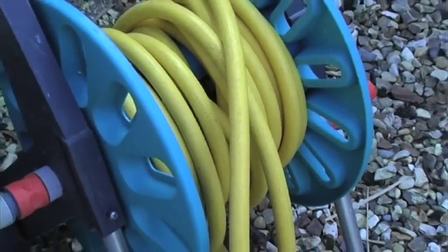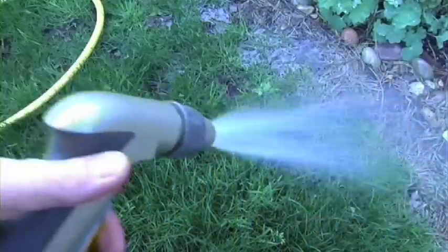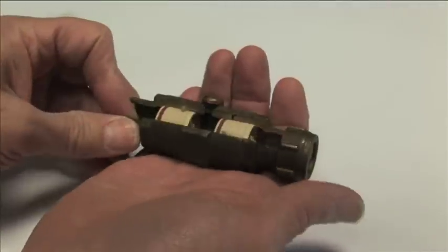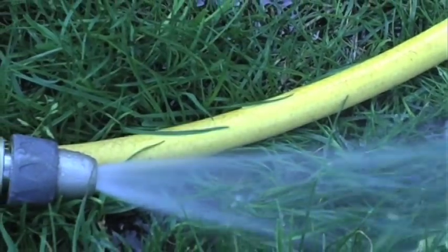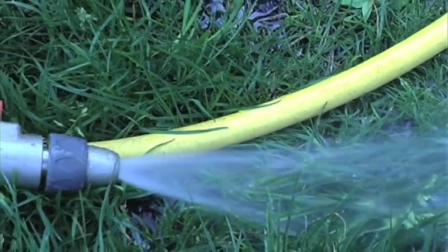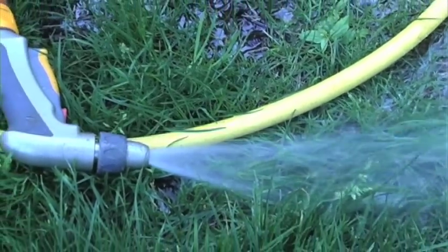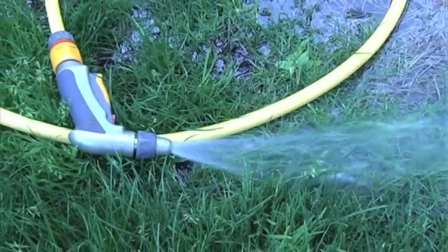In domestic premises, hose taps are usually connected directly to the water main. If mains pressure falls, to prevent backflow, they must be protected by a double-check valve — a sort of non-return valve which stops water flowing backwards in the pipes. Also, by law, hoses must be hand-held and have a trigger gun-type flow control which automatically stops the flow when it's released, and they should never be left with the end submerged in anything.